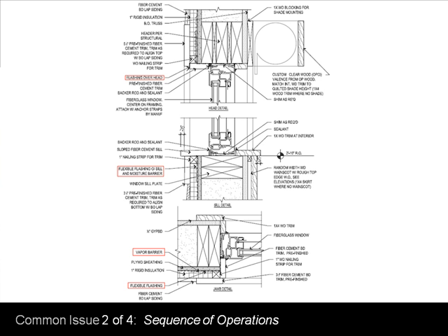Think about 3D. This is a simple cut through a wall section. What happens when you hit an inside and outside corner? What happens when you hit a water table or a pier in the structure or some geometry like that? As George said with respect to mechanical systems, people think in components. Most trades are very myopic, so they're just looking at their glass or their sealant or their air control layer. What we really have to do is start understanding these things as a full assembly. Air tightness, water tightness, vapor tightness are things that have to be continuous throughout the building. We keep coming back to the word continuity, that all these things actually have to tie together.